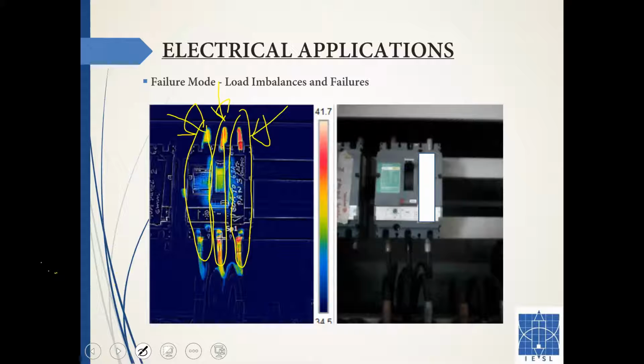It's not as simple as removing the terminal and reinstalling it. You need to do some investigation, measure the currents, see how large they are, and figure out why the currents are low on one leg and higher on the other. You need to transfer some loads around and follow up with imaging again to make sure it's properly loaded and balanced.